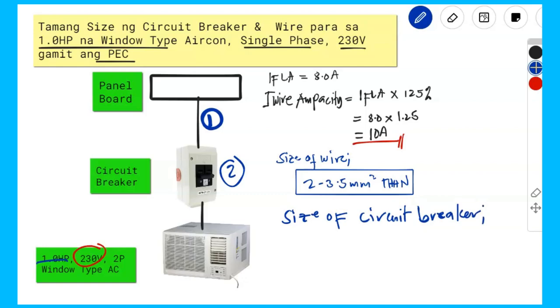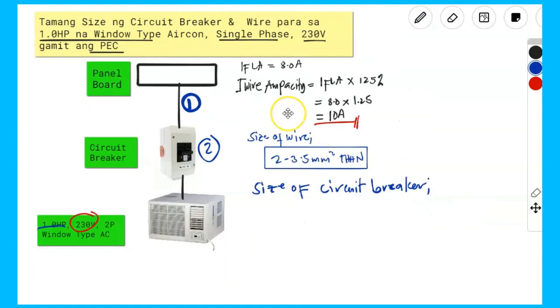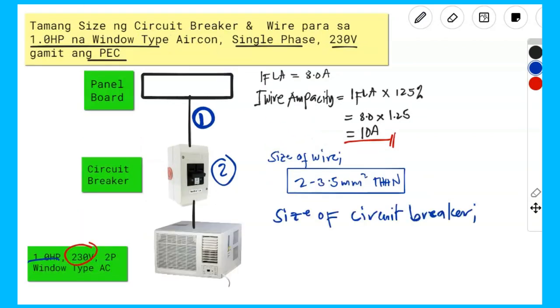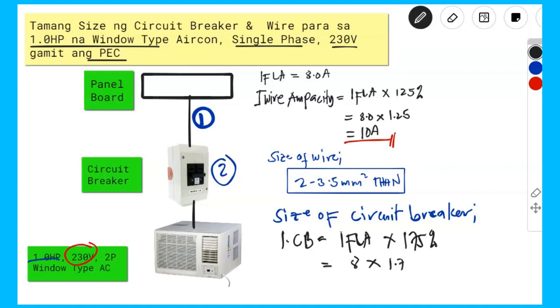Ang sabi kanina na dapat ang kanyang protective device shall not exceed 175% and di rin nalagpas sa 225%. Okay, so let's solve. So from this, for the circuit breaker, yung full load current natin ay FLA times 175%. So yung full load current natin, that is 8, times 1.75. So kung gagamit ka ng calculator, the answer is 14 amperes. Okay?